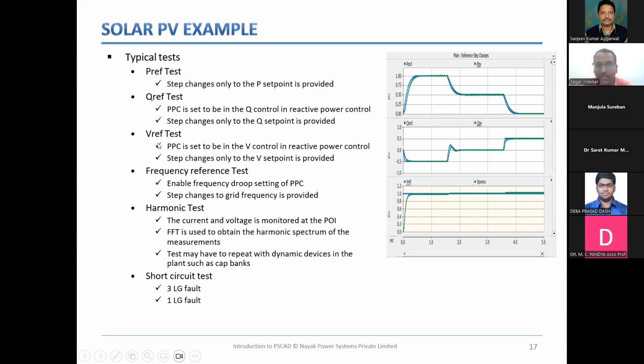Similarly, you have your voltage reference test. Now, typically, when we say voltage reference test, the grid code requirements in India don't require you to have voltage control as such, but they require you to have voltage droop control. So when I say droop control, what it means is disturbance control. Whenever the grid voltage deviates from the rated voltage and a certain set point, the PPC should inject certain Q or reduce certain Q so that the voltage is maintained. So we don't have voltage reference, we have voltage droop reference for the Indian requirement. But nonetheless, the PPC can still have voltage reference control mode already in the features.